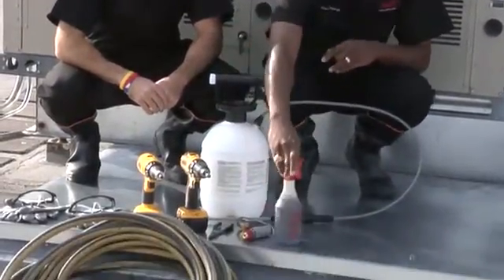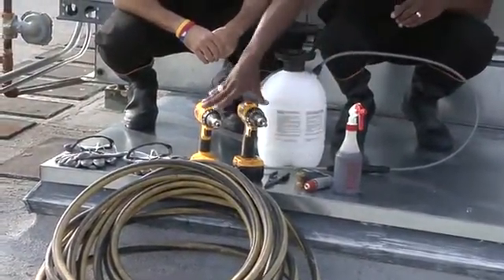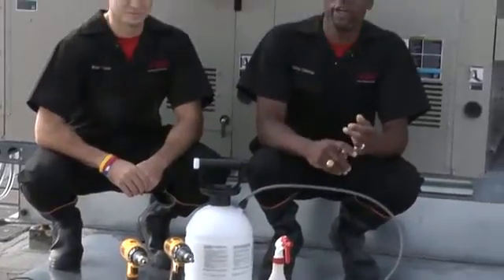The tools that are required to clean the tube and fin condenser coil will be the pump-up sprayer, coil cleaner, nozzle, needle nose pliers, two drills, two technicians, and water hose. And there might be a situation where you might need a pressure washer, depending on the amount of dirt that's on the coil, and also the water supply.